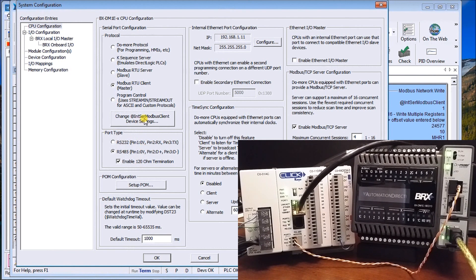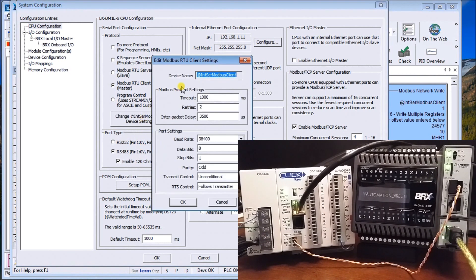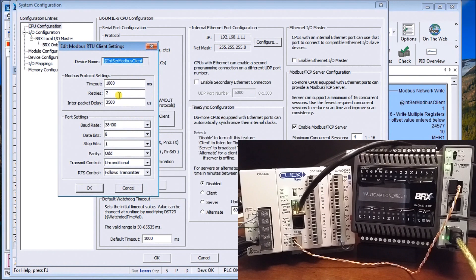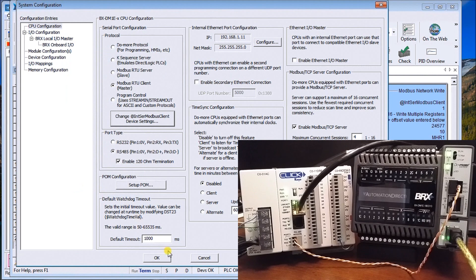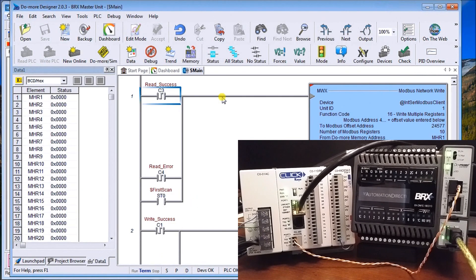Let's verify the change settings: we have 38.4k baud, eight data bits, one stop bit, and odd parity — which is exactly what we had on our Click. It's very important to make sure that they're identical in order for communications to work. We'll confirm those settings.